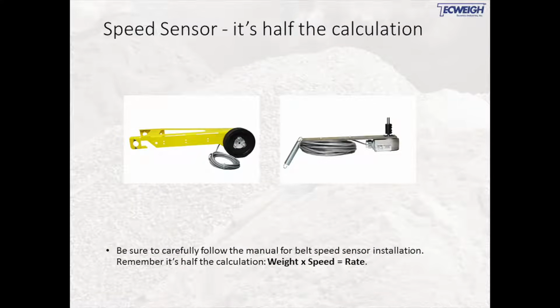A trailing arm speed sensor is commonly provided with Tecweigh belt scales. Make sure the speed sensor is located in an area on the return belt to reduce bounce. Sometimes you may have to use a snubbing pulley to reduce bounce on the return belt as well. A shaft-mounted speed sensor is sometimes supplied based on the application or customer preference. It can be installed on a bend pulley or tail pulley. Just make sure to follow the mounting instructions in the manual. Remember, speed is half the equation, so proper selection and installation is important.